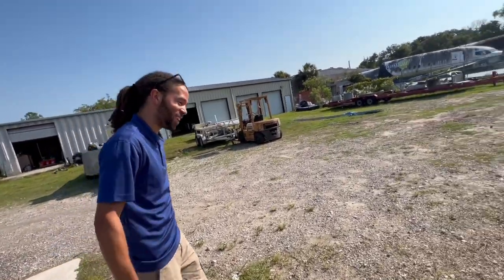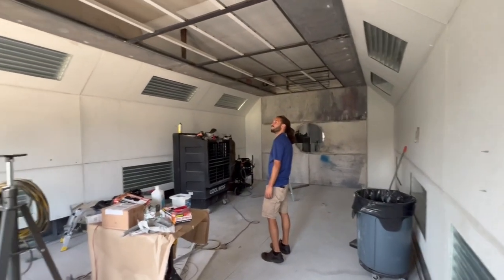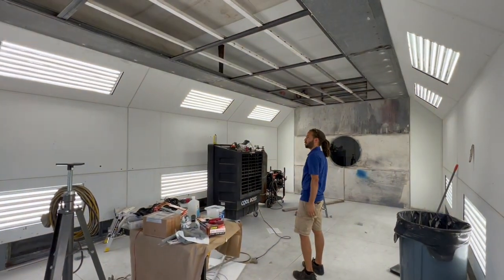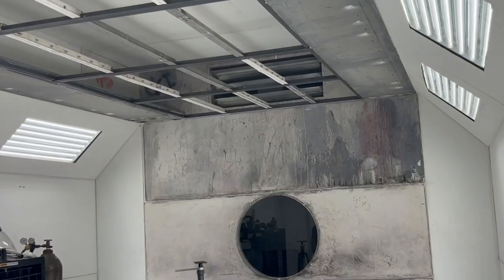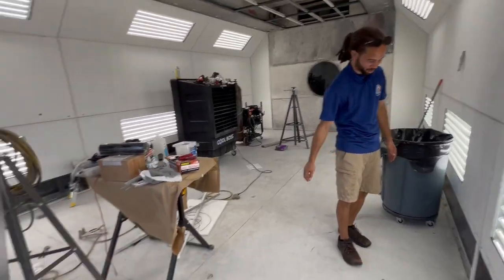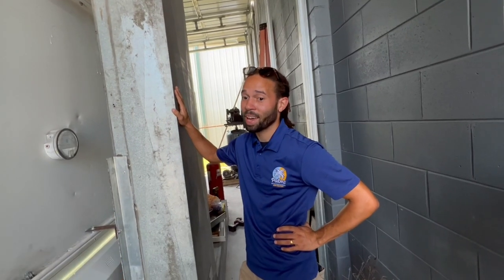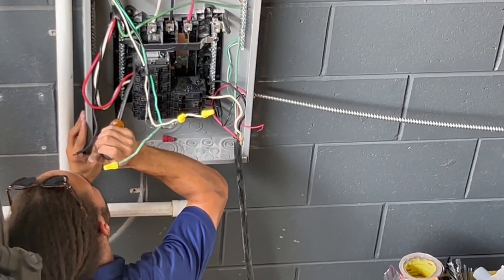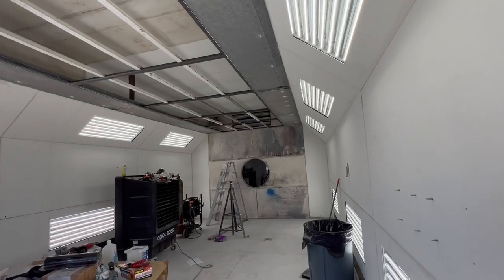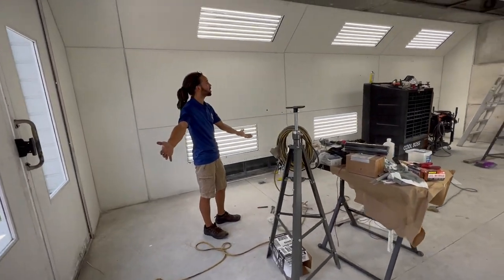I look pretty beat since the last time Lonzo was here. He hasn't even seen it run yet. After five minutes of going through everything, we figured out that the motor for the air makeup unit was actually spinning backwards. We had to turn it the other way — but once we swapped it around, this is exactly what we needed.